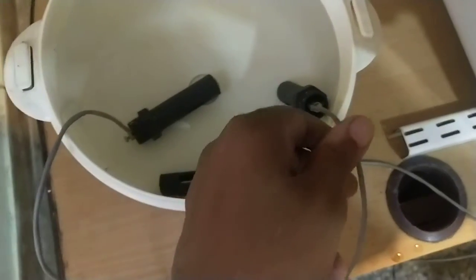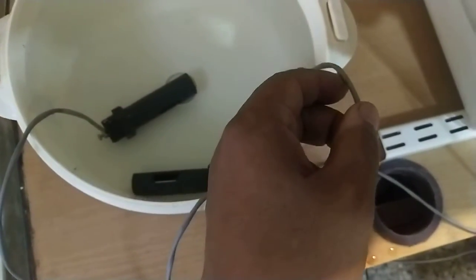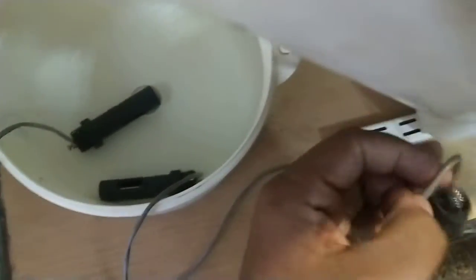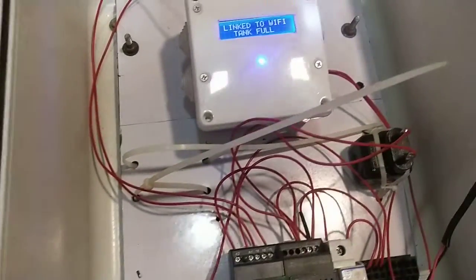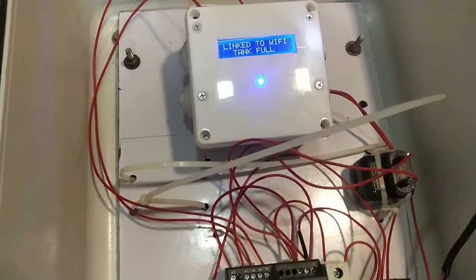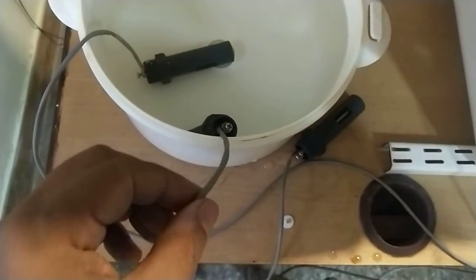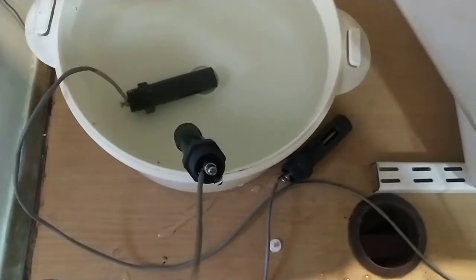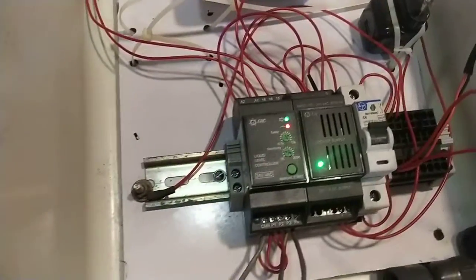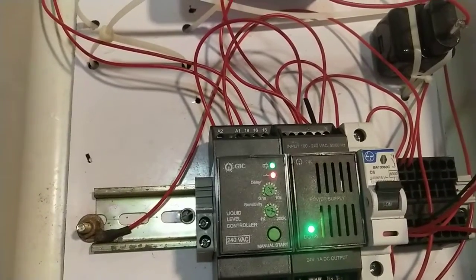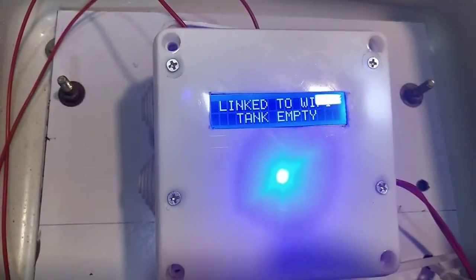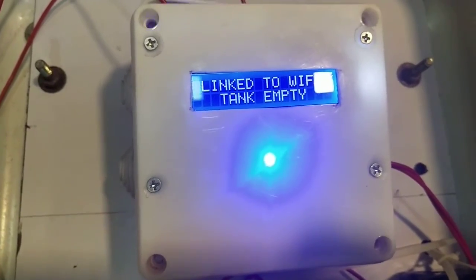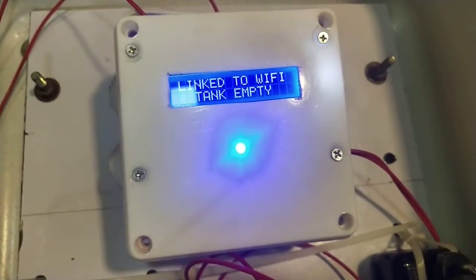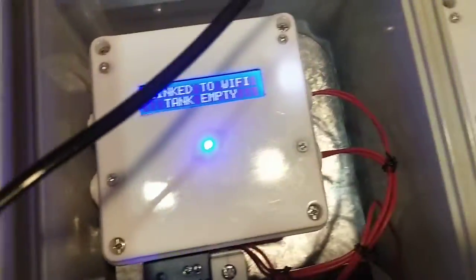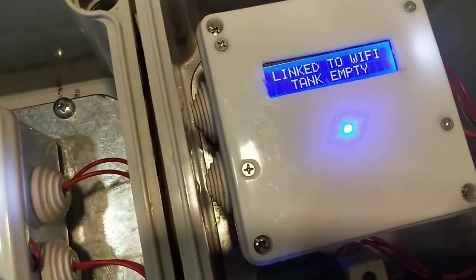Now what happens if I remove the probe here? I remove the high probe. The tank full signal is still there. When I remove the middle probe or the low probe, the tank empty signal has now come on. The tank empty signal is being uploaded to the cloud by the U-link at the tank end. So this tank empty signal has appeared everywhere at all the 3 pumps.